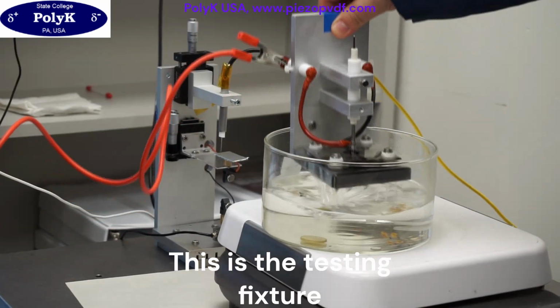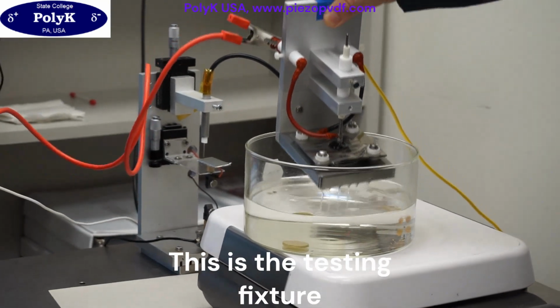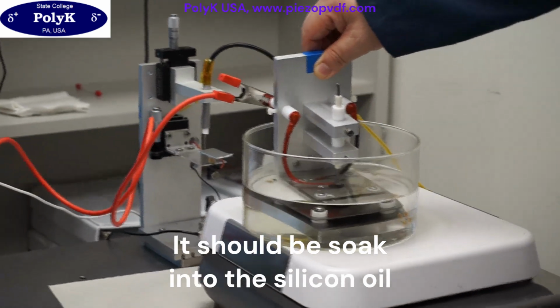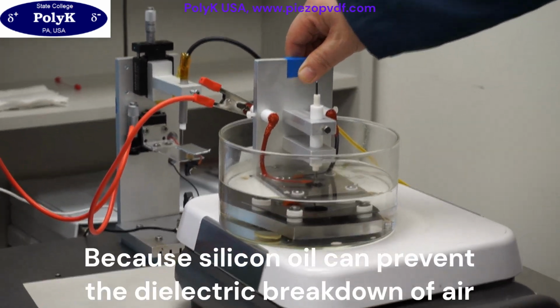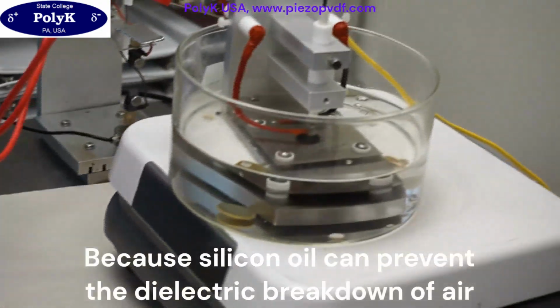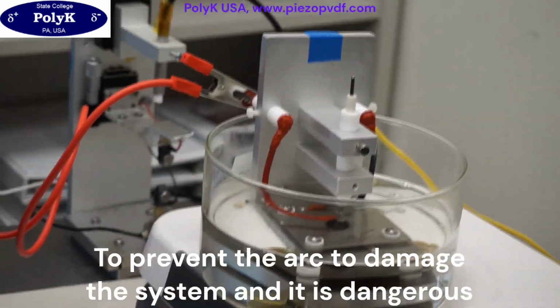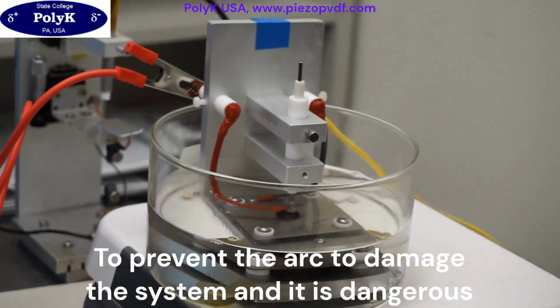And this is the test fixture. You see here, you soak it into silicone oil, because silicone oil can prevent the dielectric breakdown of air and prevent the arc. The arc may damage the test system and is also dangerous.